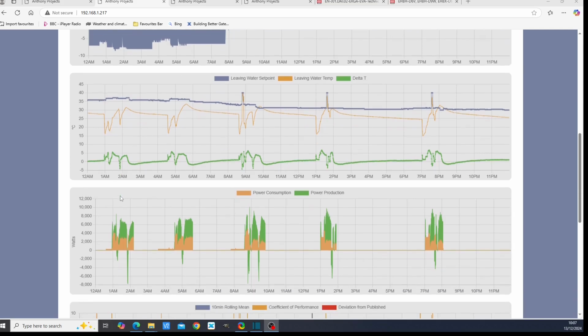Generally speaking, a weather-dependent temperature set point for your leaving water temperature relies on a constant temperature set point for your internal house temperature, and that's going to be 21 degrees Celsius. So if you then change the set point of your house down to 12 degrees Celsius in this instance, then you need a different weather-dependent curve in order to get the most efficient use out of your heat pump. And unfortunately, the Daikin does not have the option of having a reversionary weather-dependent heat pump curve for different temperature set points which you may have in your house.